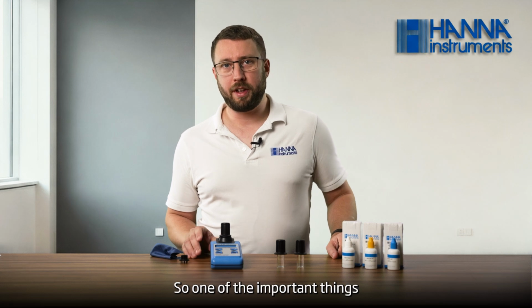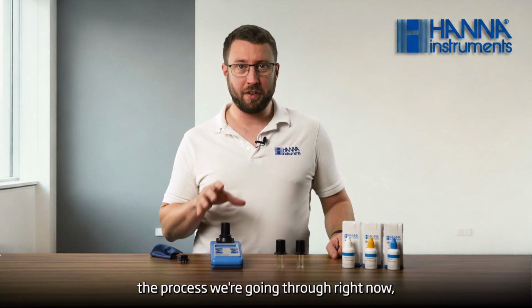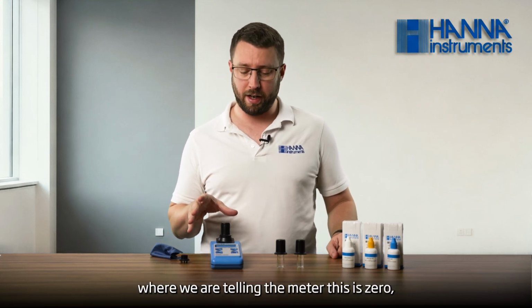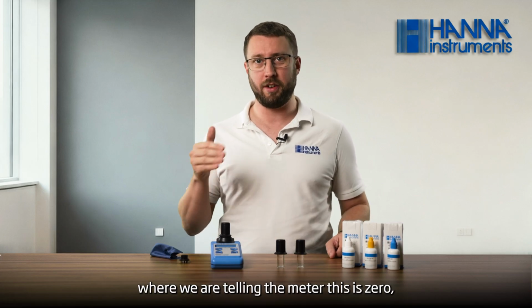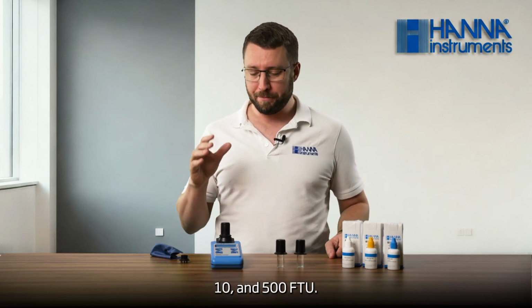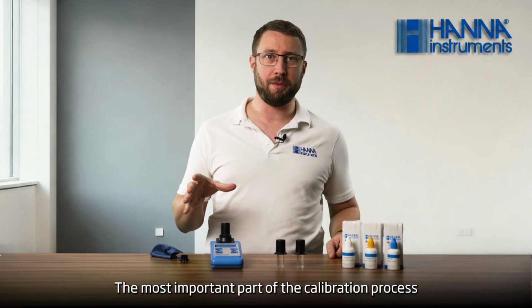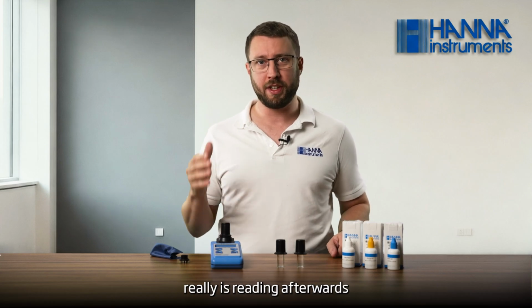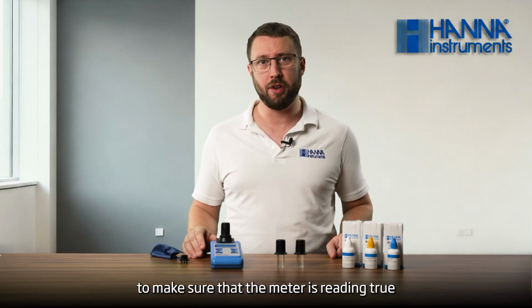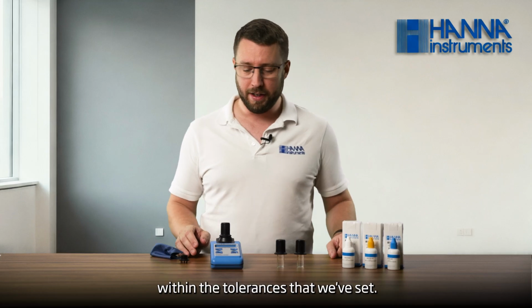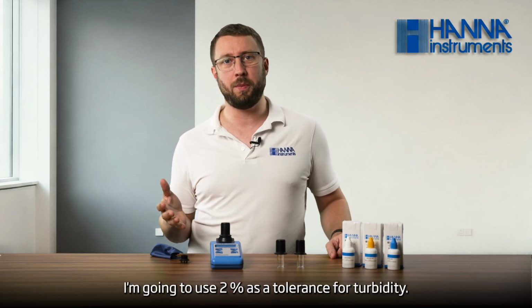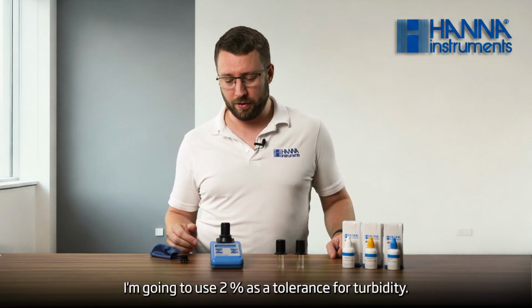So one of the important things with the calibration of the meter isn't necessarily the process we're going through right now, where we are telling the meter this is 0, 10 and 500 FTU. The most important part of the calibration process really is reading afterwards to make sure that the meter is reading true within the tolerances that we've set. So as an example, I'm going to use 2% as a tolerance for turbidity.